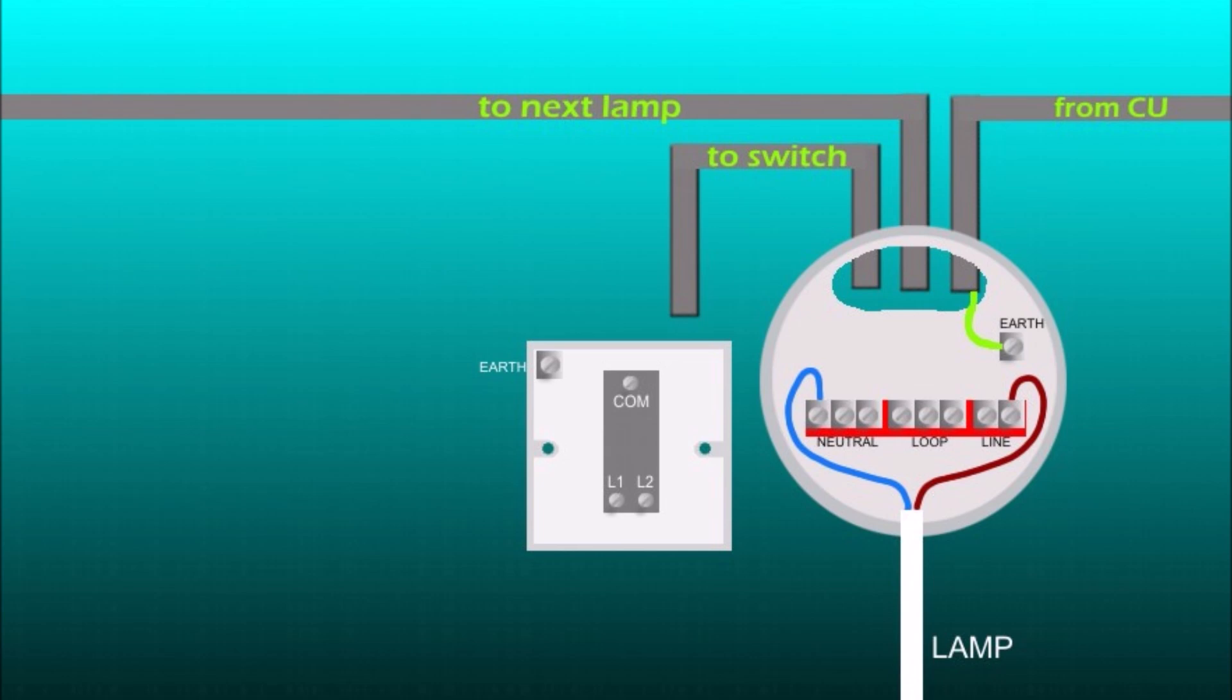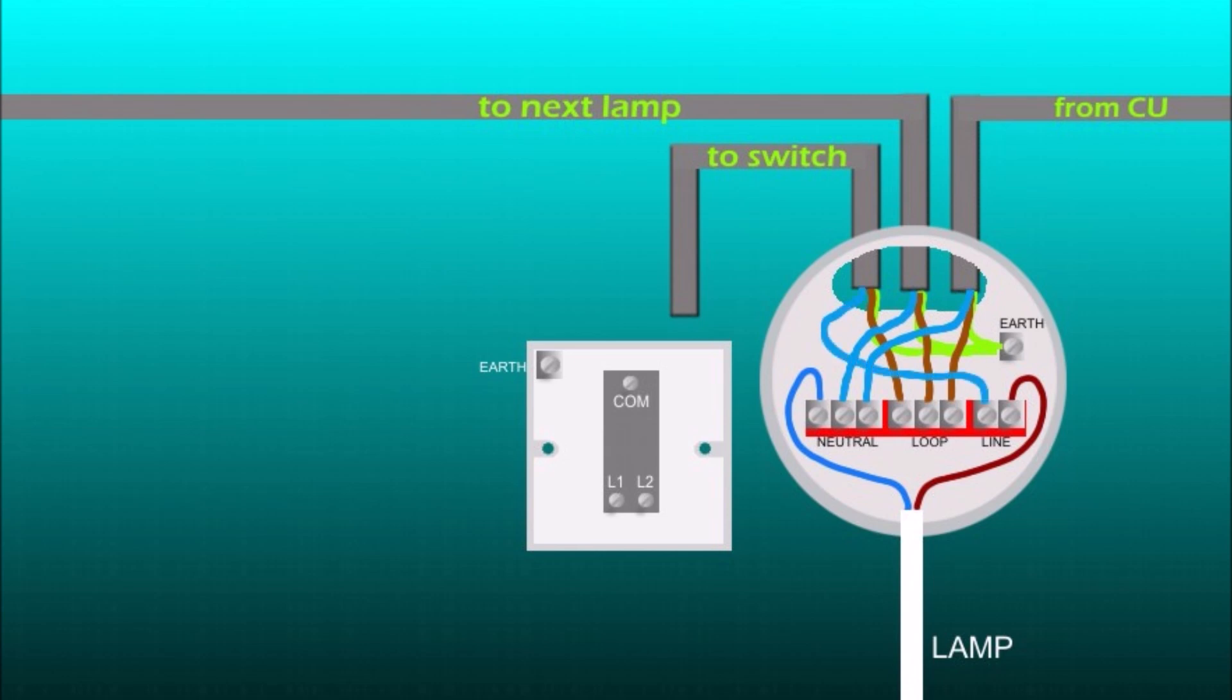So as you see at the ceiling rose you've got three cables, one from consumer unit, one is going to the next lamp and one is going to the switch. So all the earth wires from all of these three cables go to the earth terminal on the right. All the brown wires from these three cables going to the loop terminal in the middle, the live wires. And the two blue neutral wires from these two cables except the switch one going to the neutral terminal on the left. And the last blue wire from the switch cable going to the line terminal on the right and you have to put a brown sleeve on it just to indicate that it's gonna be live as well.